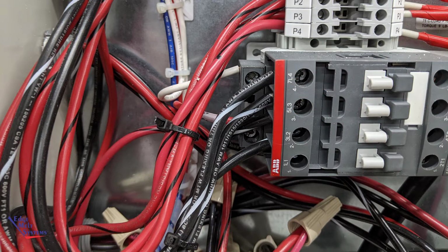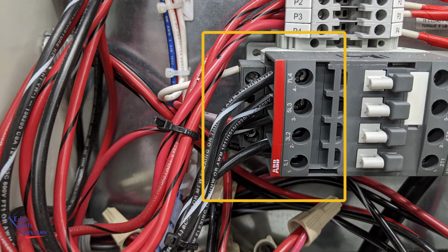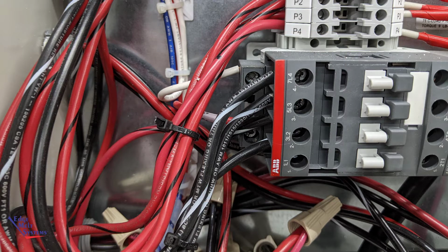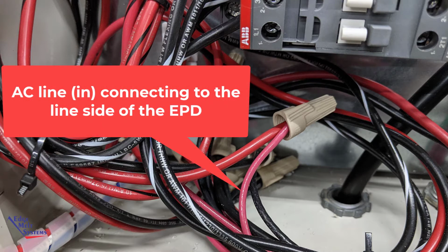Again, a close-up showing the load side of the EPD or power coming in on the line side of the controller. And for reference, when using the EPD units, we see here connection from line coming in to the line side on the EPD unit, which is indicated by the solid red and solid black wires here on this 240 volt EPD. They will be white and black solid on 120 volt EPDs.